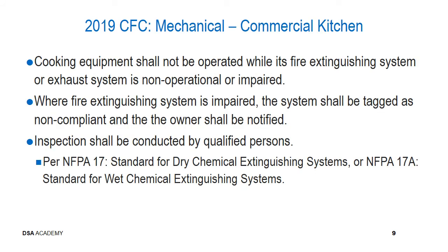Cooking equipment shall not be operated while the fire extinguishing system or exhaust system is non-operational or impaired. Where fire extinguishing systems are impaired, the system must be tagged as non-compliant and the owners must be notified. Inspection of commercial kitchen hood systems must be done by qualified persons, following NFPA Standard 17 for dry chemical extinguishing systems and NFPA 17A for standard wet chemical fire extinguishing systems.